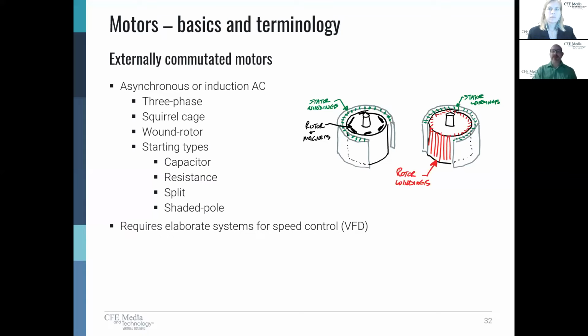The main concept of an asynchronous or induction motor is that it never runs at synchronous speed. It's always going to have a little bit of slip, meaning it's always going to be slightly slower than what it could be in an ideal world. And that's actually a design requirement, because that slight bit of difference is what generates current within the rotor and therefore allows for that changing magnetic field.